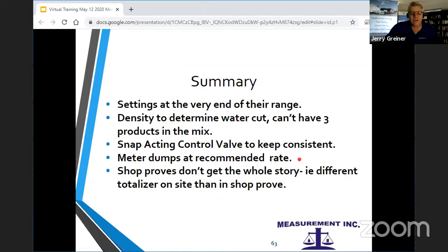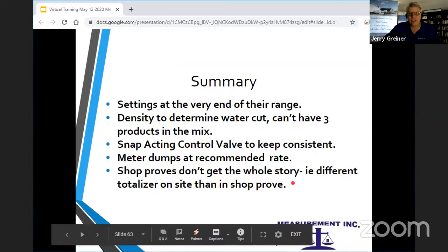And what you want on the meter rate, I get this question over and over, is the instantaneous dumping rate. That's what we're worried about. I'm not worried that the well makes 3 cubes a day and it's got a meter that has to dump 27 cubes a day. We're worried about the rate when it's actually dumping. It should be over the meter rate, not when it stops. So it can dump 27 cubes a day for 10 seconds and then be stopped for 10 minutes. That's just fine. It's the meter recommended rate. And then shop proves don't get the whole story.